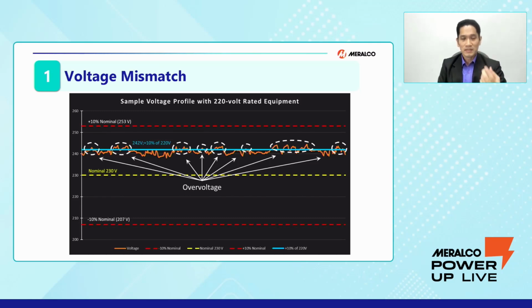Using the same voltage profile, the horizontal blue line is the plus 10% of the 220 volt rated equipment. It means that all voltages above the blue line will already subject our 220 volt rated equipment to overvoltage, even though the supply voltage is still within the 10% allowable variation of 253 volts. Our equipment is already subject to overvoltage.